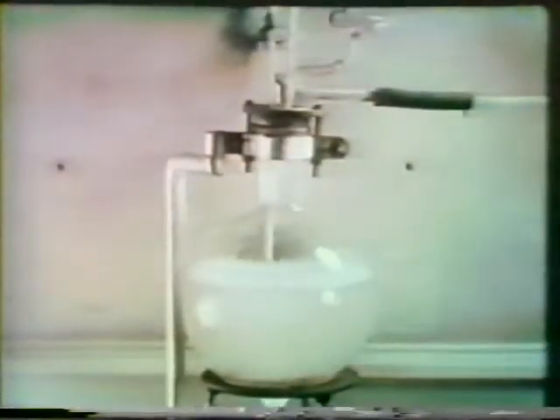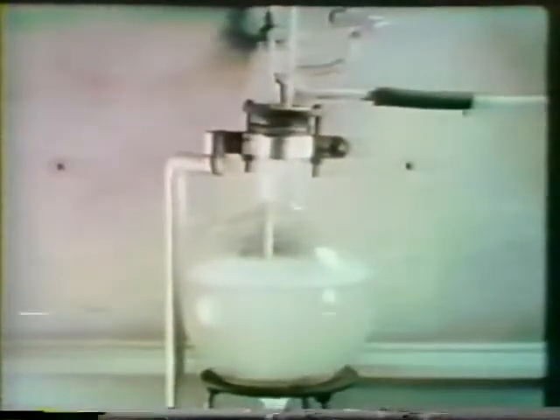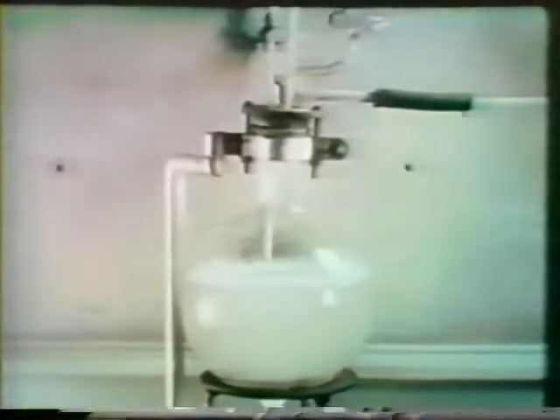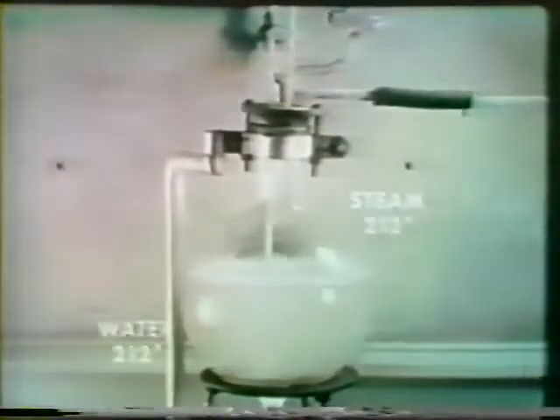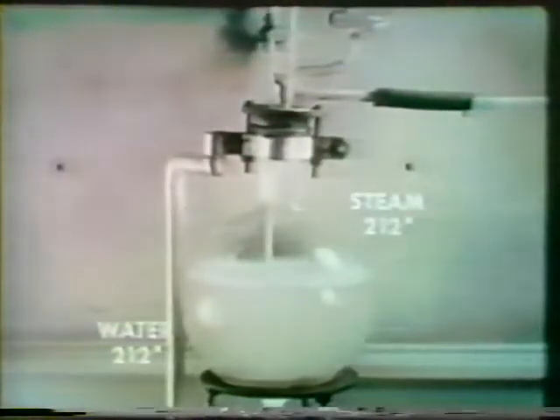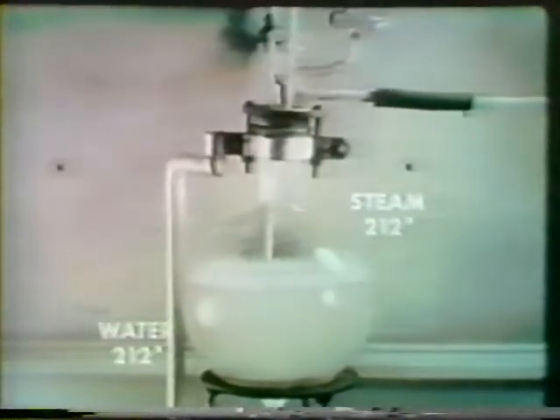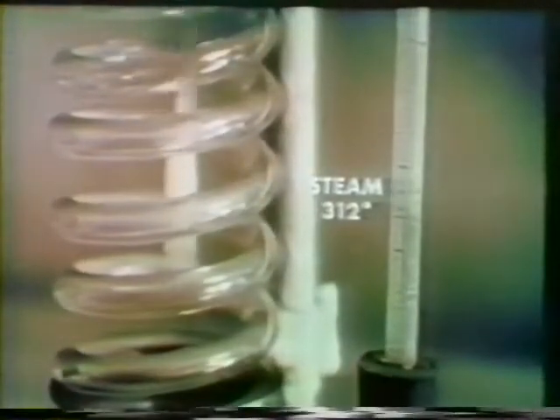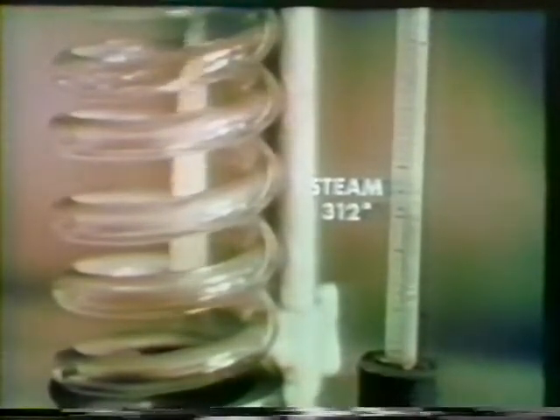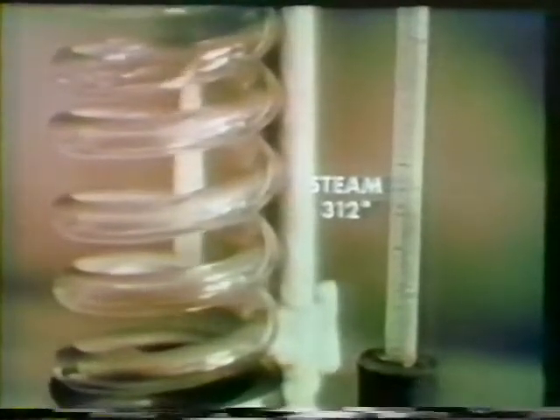This laboratory model shows saturated steam being produced. Saturated steam will have the same temperature as the boiling water, in this case 212 degrees Fahrenheit. No amount of heat can raise the temperature of the steam higher than that of the water with which it is in contact. However, if tubes are located away from the water, the saturated steam flowing through them can be heated to a much higher temperature. In this case, the steam has been raised to 312 degrees Fahrenheit. The process of adding heat to saturated steam is called superheating.